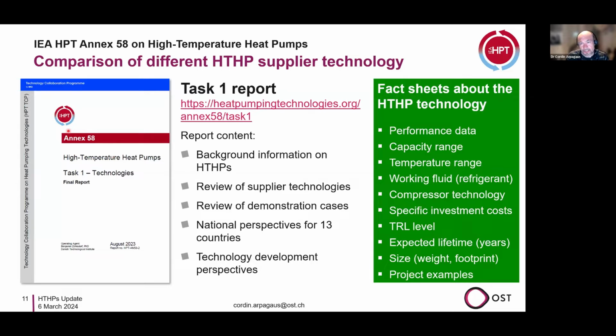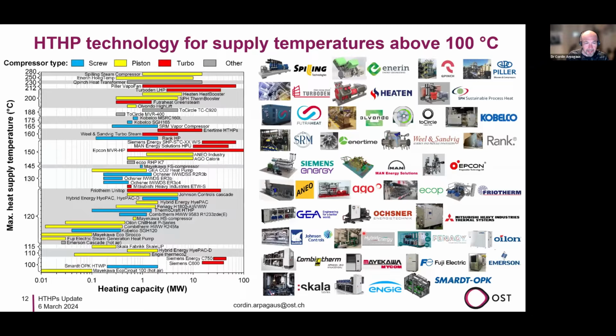What I'm especially interested in is the fact sheets on the technologies, which include performance data, capacity ranges, temperature range, working fluid/refrigerant used, compressor technology, investment cost, TRL level, lifetime, size, and examples. This slide tries to summarize a lot of this report, and also includes some additional companies and manufacturers of high temperature heat pumps which are not in the report - so it's a state of the art overview.